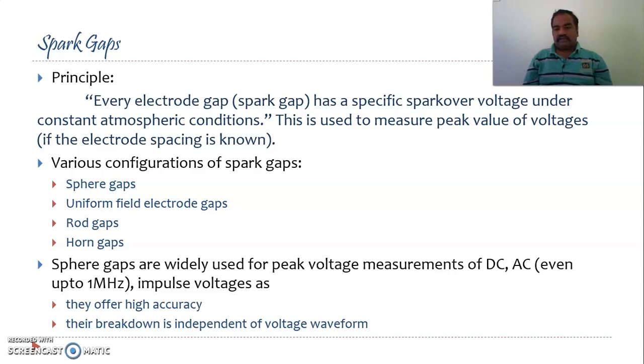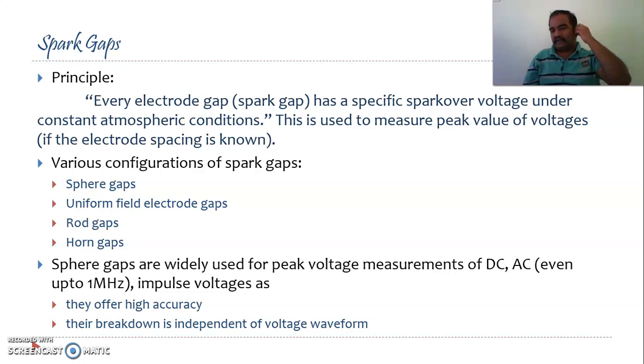Out of all these different electrode shapes, sphere gaps which employ spheres as electrodes are extensively used for peak measurement of DC, AC, and impulse voltages. This is because they offer very high accuracy and the breakdown of the sphere gaps is independent of the voltage waveform. That is why sphere gaps are widely used over uniform field electrode gaps and rod gaps.